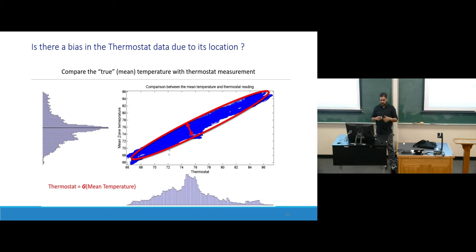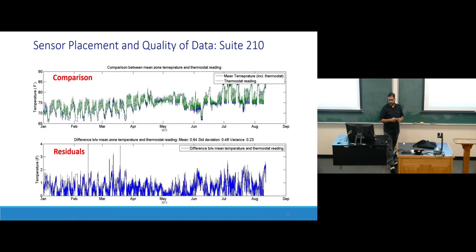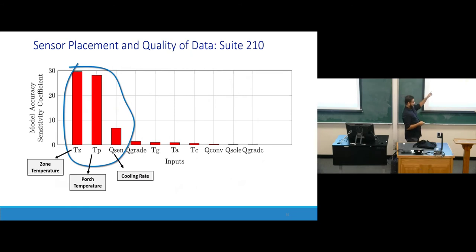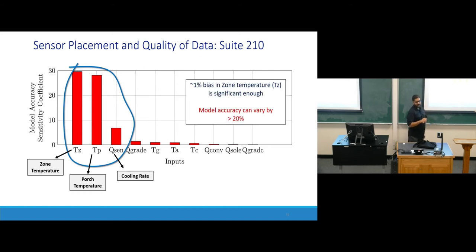Skipping some analysis, you can fit a Gaussian curve around this uncertainty to measure the extent of the bias. We found about a 1% bias between what the thermostat reports and the mean. Naively you might dismiss 1%, maybe just 0.2 to 0.5 degrees, as nothing. But the sensitivity analysis shows the zone temperature is the most influential variable, and a 1% bias there can influence model accuracy by more than 20%.